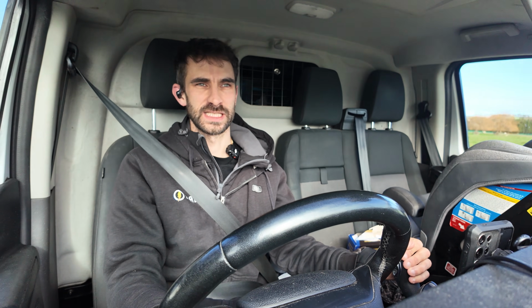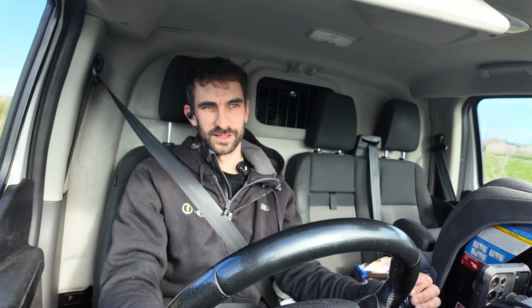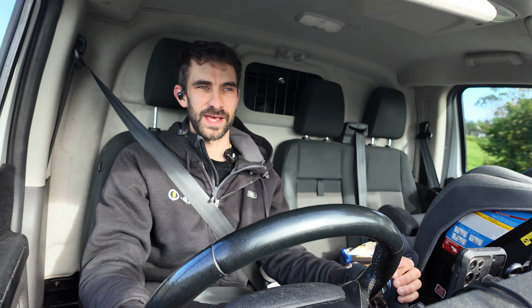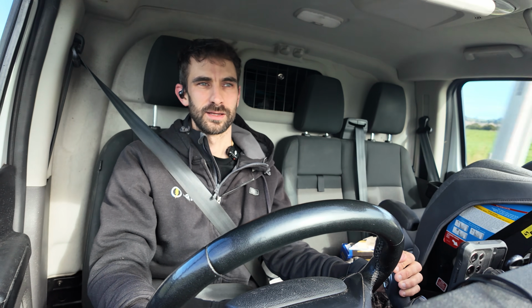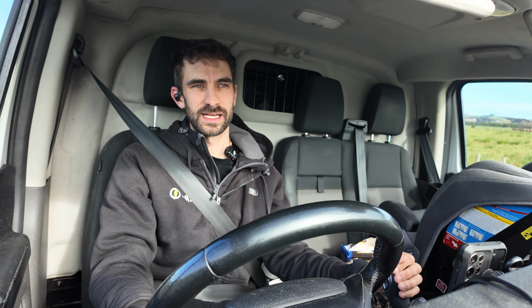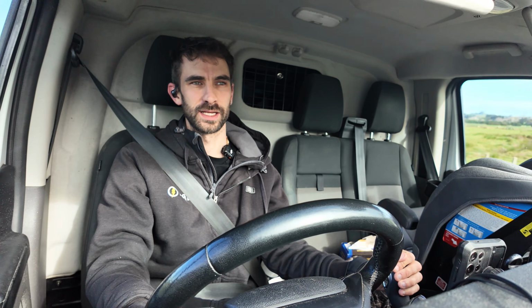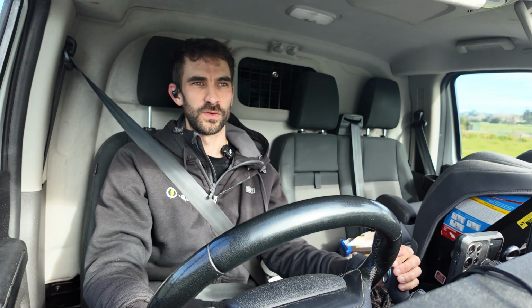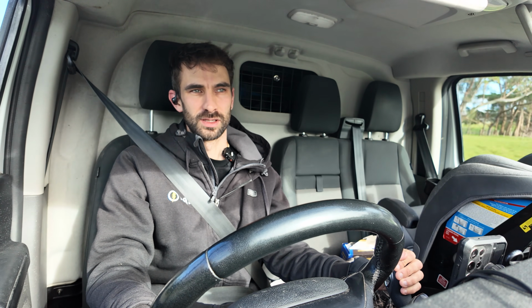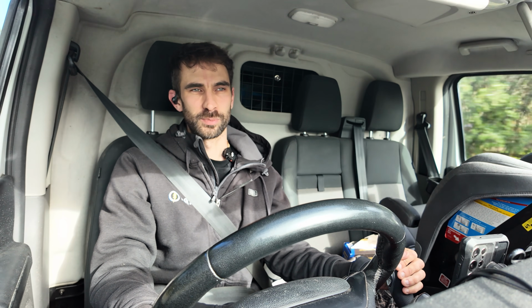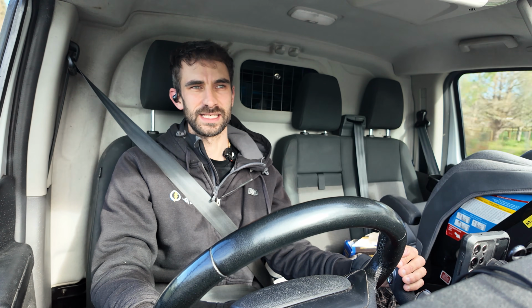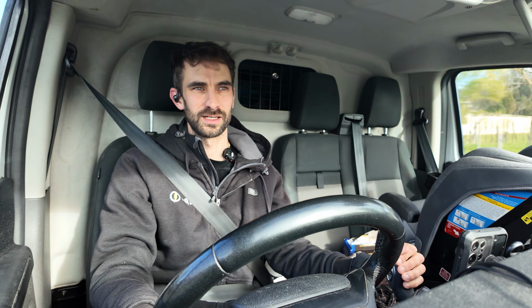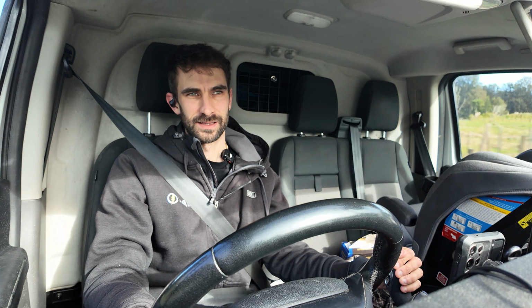Which brings me to one of my big arguments against the value of the earth rod. Everything we put in for electrical safety, we can pretty much mathematically describe what it's doing, how it functions, and at what point of failure it stops performing its required job. So we do earth fault loop impedance tests to make sure that under fault conditions, the breaker is going to trip fast enough. We test RCDs to make sure they're tripping quickly enough under certain test conditions, and so on.